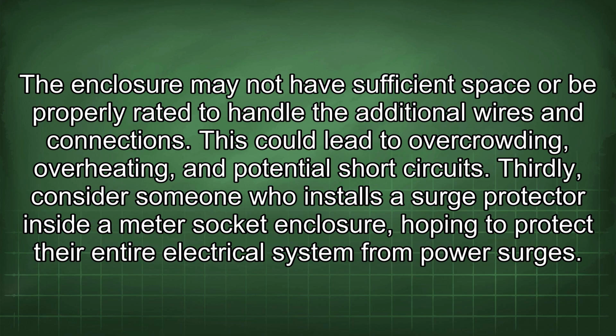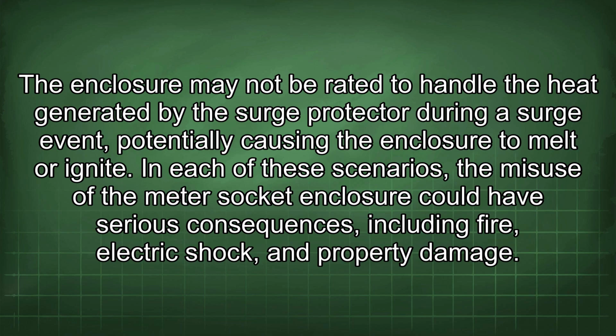Thirdly, consider someone who installs a surge protector inside a meter socket enclosure, hoping to protect their entire electrical system from power surges. The enclosure may not be rated to handle the heat generated by the surge protector during a surge event, potentially causing the enclosure to melt or ignite.